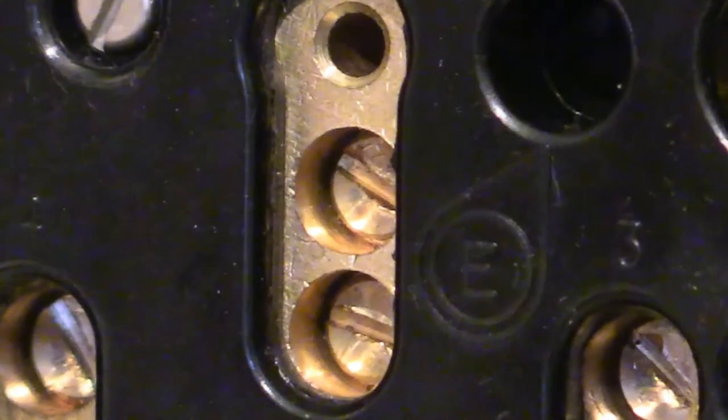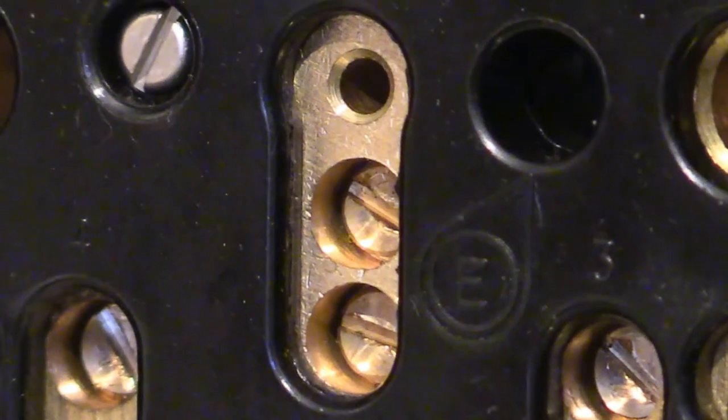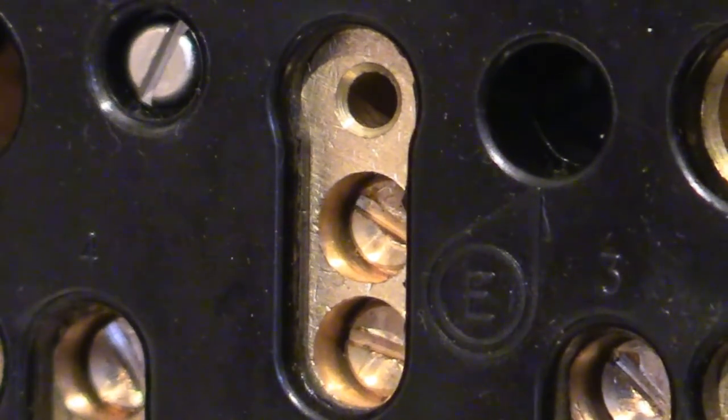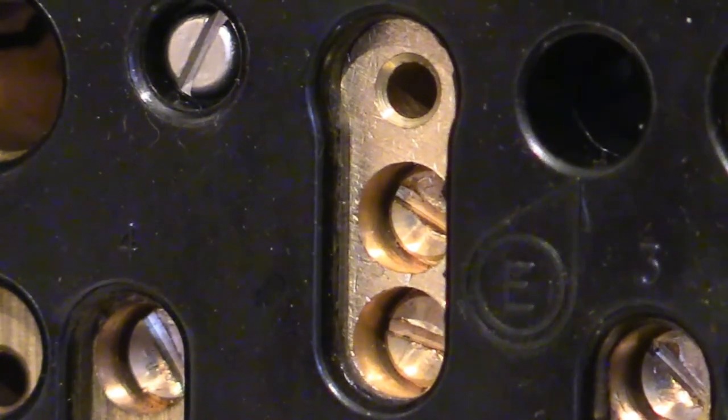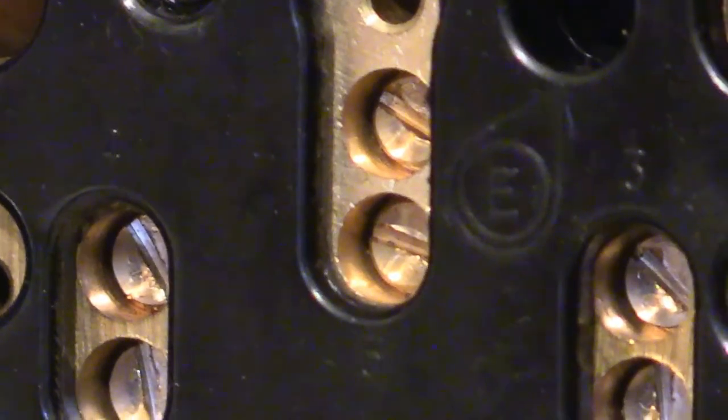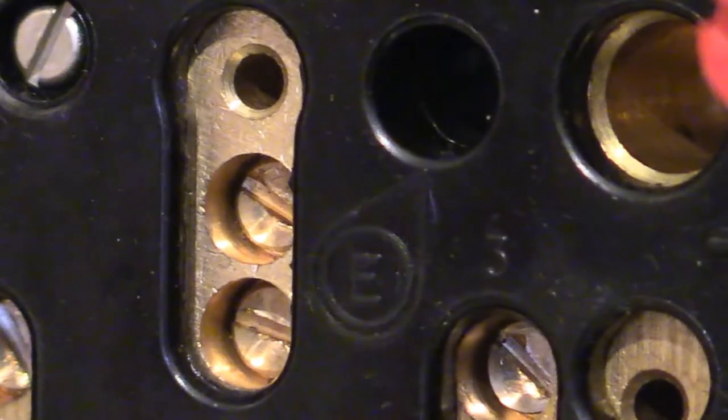The next one along, you can see another pin hole there and two terminal screws below it. That is for the rate change trigger pin. That terminal is only available on the VMK 7. On the VMK 5 and the VMK 4 and even the VMK 2, that location is blanked off. Just inside there you can see letter E, and there's an arrow pointing up to it. Inside that hole right there, there's a terminal screw down there, and that is for the earth terminal. On these, the earth terminal is that metal part sticking up. When you plug the time switch in, the metal case of the time switch rubs up against that and provides an earth connection.